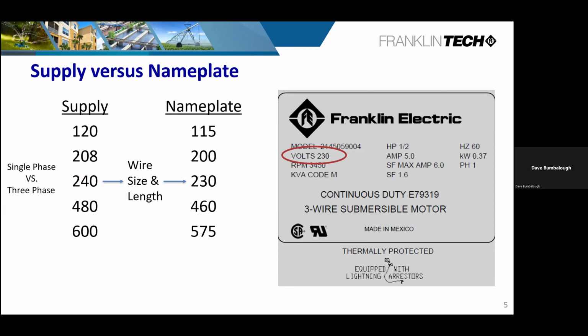Nowadays, because of us as consumers, and the fact that they have branched out pretty much everywhere nationwide, you don't have too many areas that do not have a power pole or some kind of voltage supply. To make sure there's voltage on those longer runs and in places that I refer to as out in the boonies, they crank the voltage up. To give you an example, about 25 years ago, when I came out in field service, I noticed that 240 volt supply voltages were constantly around 245. Now, 20 years later, I notice that they're hovering around 250.